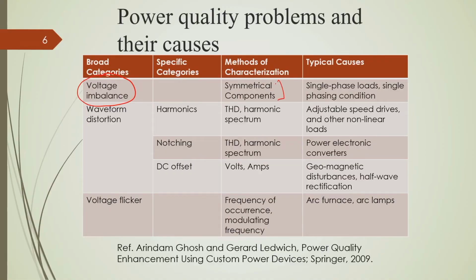So, if any parameter deviates, meaning that if the voltage of any phase is much higher or lower than the other 2 phases, then it will cause a voltage unbalance. Similarly, even if we have the same voltage magnitudes, if they are not 120 degrees apart from each other, then it will also cause voltage imbalance. I will discuss this; it is characterized by a well known method called symmetrical component analysis. The reasons for this voltage imbalance are single phase loads and single phasing conditions. Single phasing condition is another type of fault.